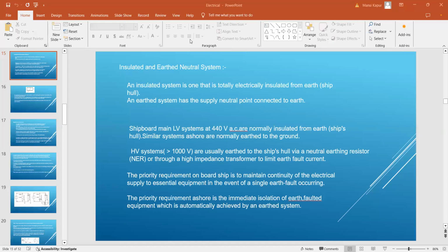Yes, sir. Because if we use the earthed system, what is going to happen? One single earth fault is going to trip your motor, right? So what about your steering gear motor? It will trip, sir. A single earth fault will trip it.